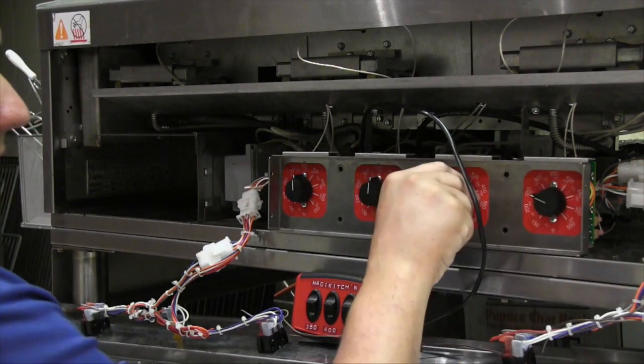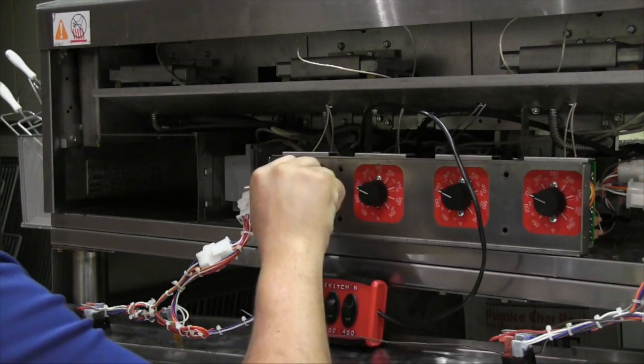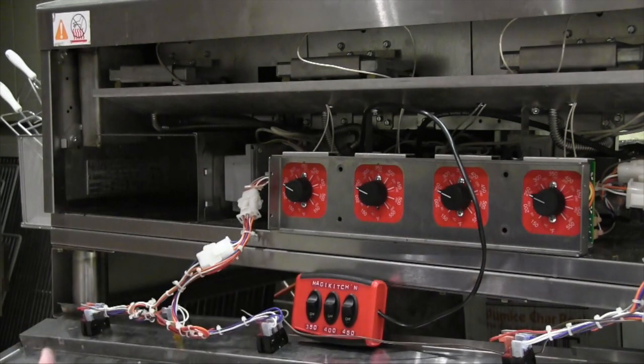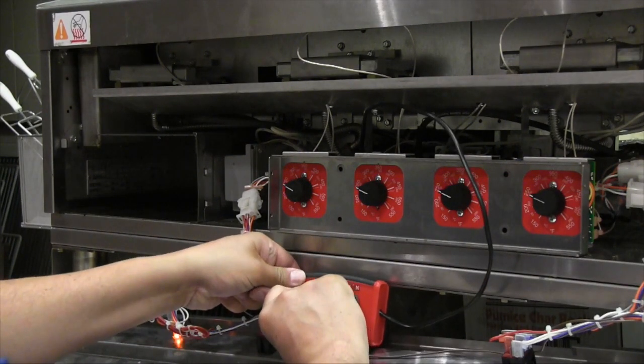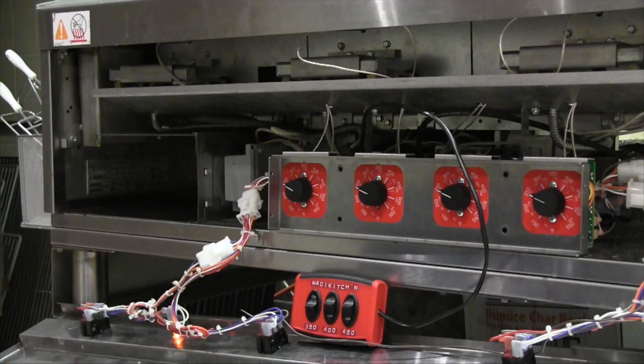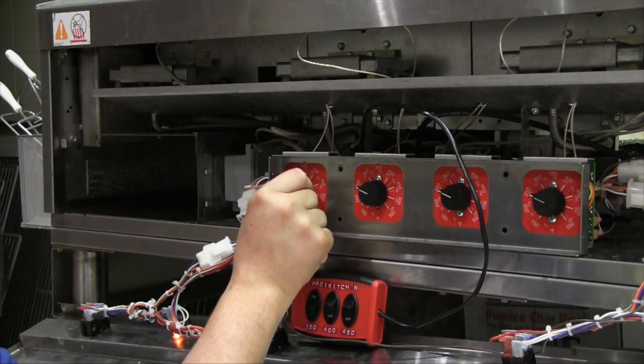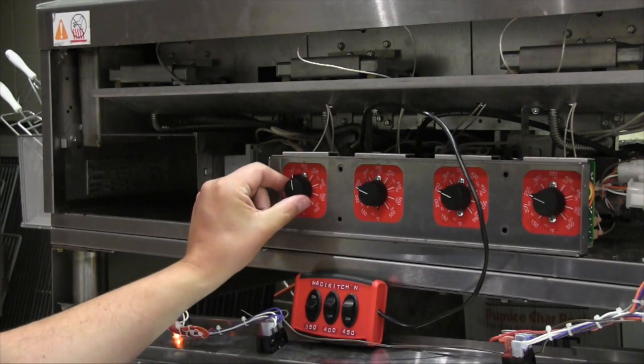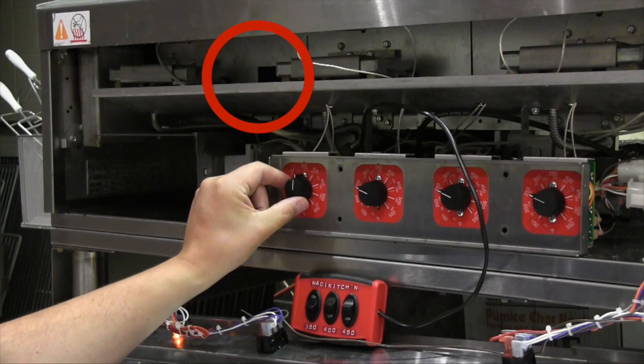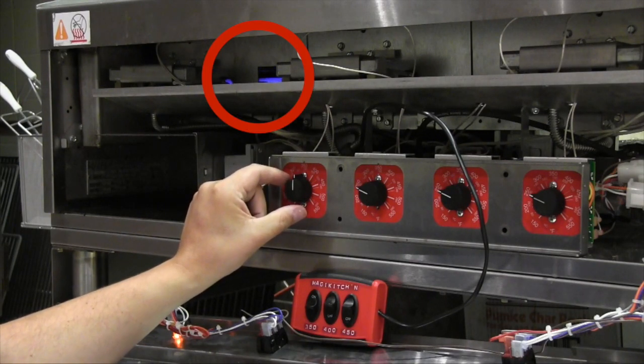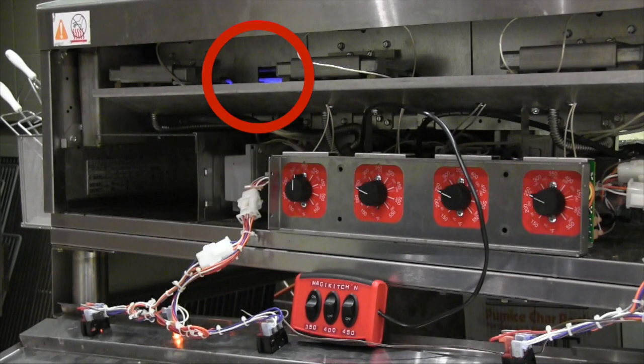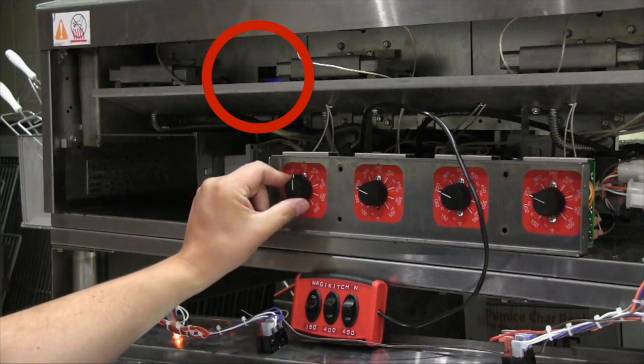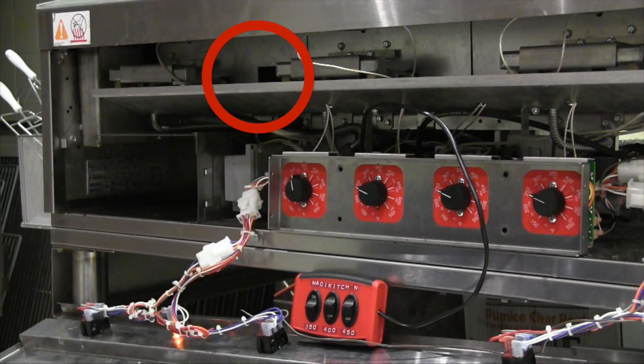Turn the control knobs to have all the controls under 300 degrees. Turn the power switch on for the controller that you are trying to calibrate. The pilot should light, but the burner should not turn on. Put the switch on the calibration tool for 350 degrees into the on position. The burner should not turn on. Rotate the knob up in temperature until the burners turn on. The pointer on the knob should be pointed at 350 degrees when the burners turn on.